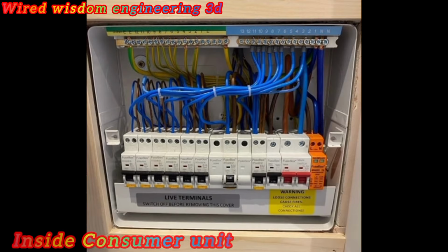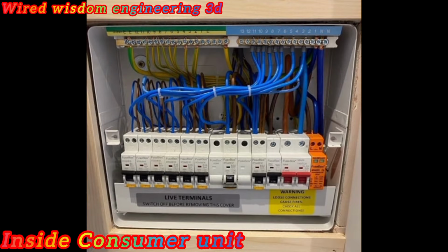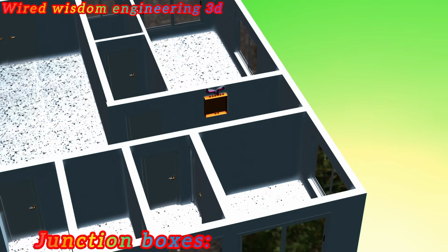Inside the consumer unit, we find a main switch used to isolate the entire installation, miniature circuit breakers, MCBs, that protect circuits from overloads and short circuits, and residual current devices, RCDs or RCBOs, designed to protect human life by disconnecting power when leakage currents are detected. Whenever a fault occurs, these protective devices trip automatically, preventing damage, fire, or electric shock. From the consumer unit, electrical conduits are carefully offset and routed to junction boxes that serve socket circuits and lighting circuits.